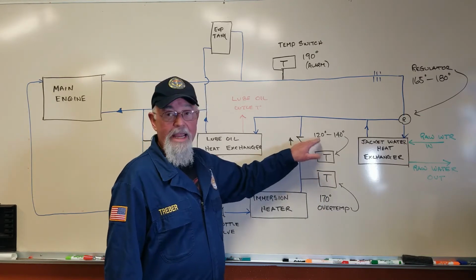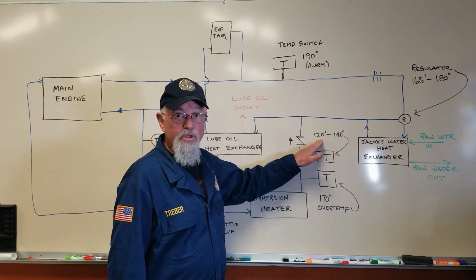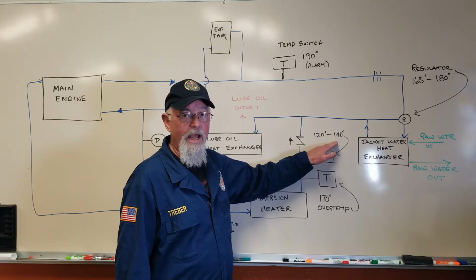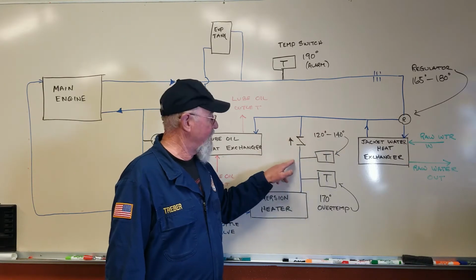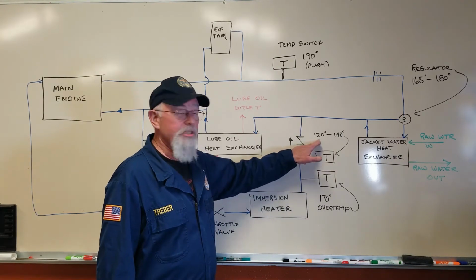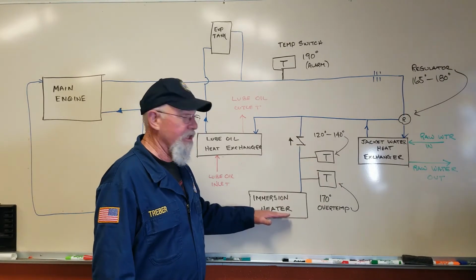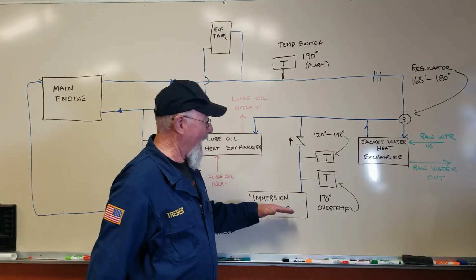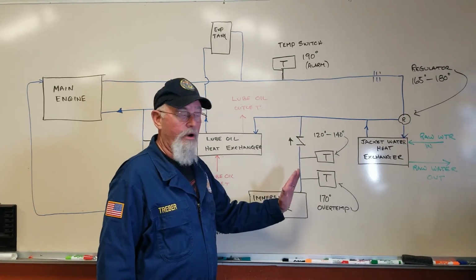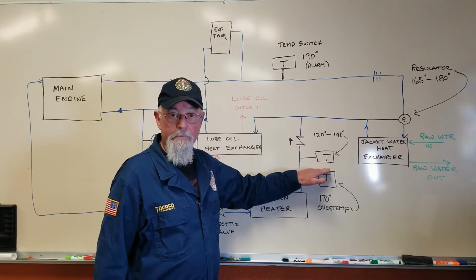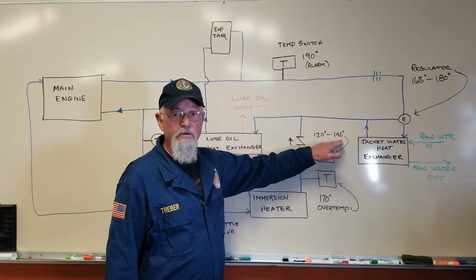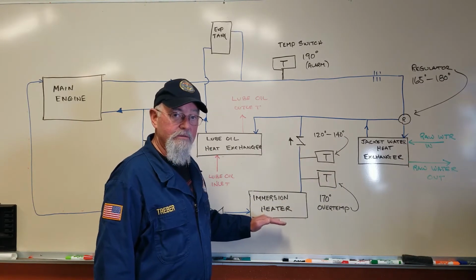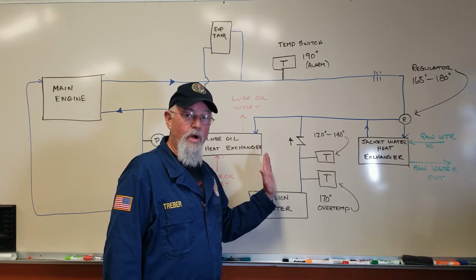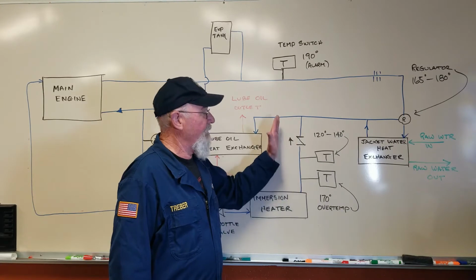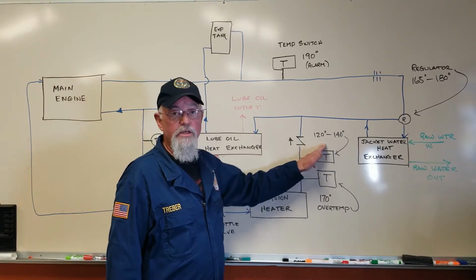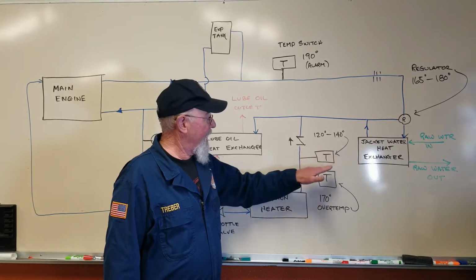The other temperature switch is our regulating temperature switch. So it's set to operate between 120 to 140 degrees Fahrenheit. Now it's not the switch that's operating, it's sensing the temperature of the water, and if the water temperature is below 120 degrees, the heating element that's immersed in the water inside the immersion heater will energize and transfer heat to the jacket water. If that jacket water temperature being sensed at this temperature switch reaches or exceeds 140 degrees, the heating element will be de-energized. And as the temperature cools again and gets to 120 or below, it re-energizes it, so it maintains the circulating jacket water temperature between 120 and 140 degrees as sensed by this temperature switch.